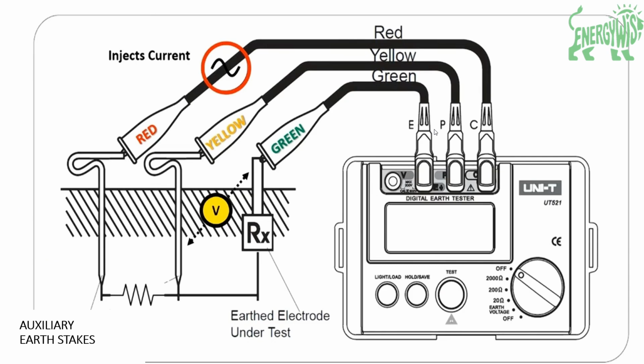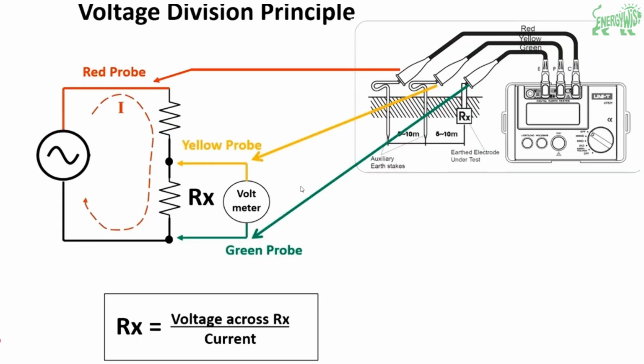After we connect them in this way, we set the selector to 20 if we expect to measure less than 20 ohms, and according to our measurement we can adjust the range here. Then we set it to 20, and when we press the test button, the red lead gives 50 volts to the ground, so that in this way we can measure. When the red gives 50 volts, there is a connection between the auxiliary spike and the ground rod, so it will be a closed circuit and there will be current flow.